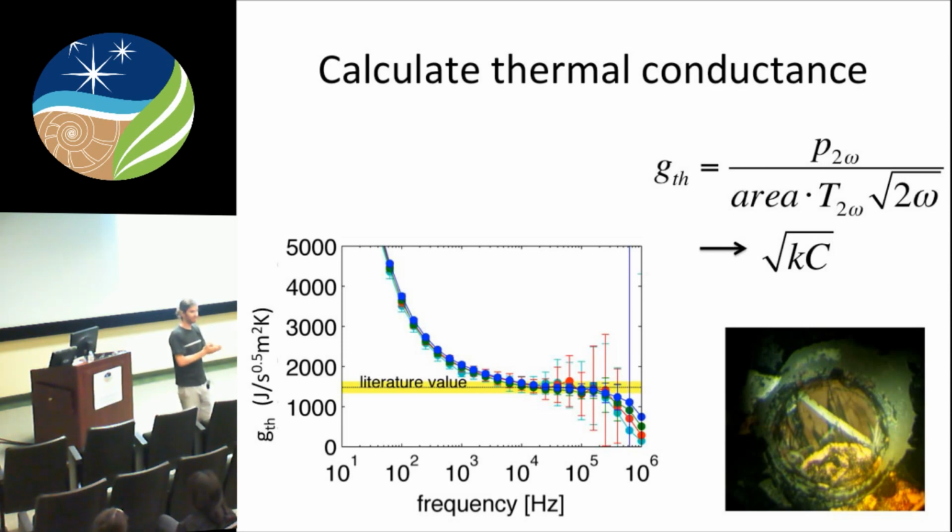When I do these faster heating runs, when I raise the DC temperature, the thing I'm going to rely on is the resistance of the heater. I don't think there's much room in diamond cells. If we put 2 pressure markers, like samarium-doped YAG, you can know both the temperature and the pressure in theory, but I don't think those scales are so well developed. I think the resistance of a metal heater is a pretty good temperature measurement.